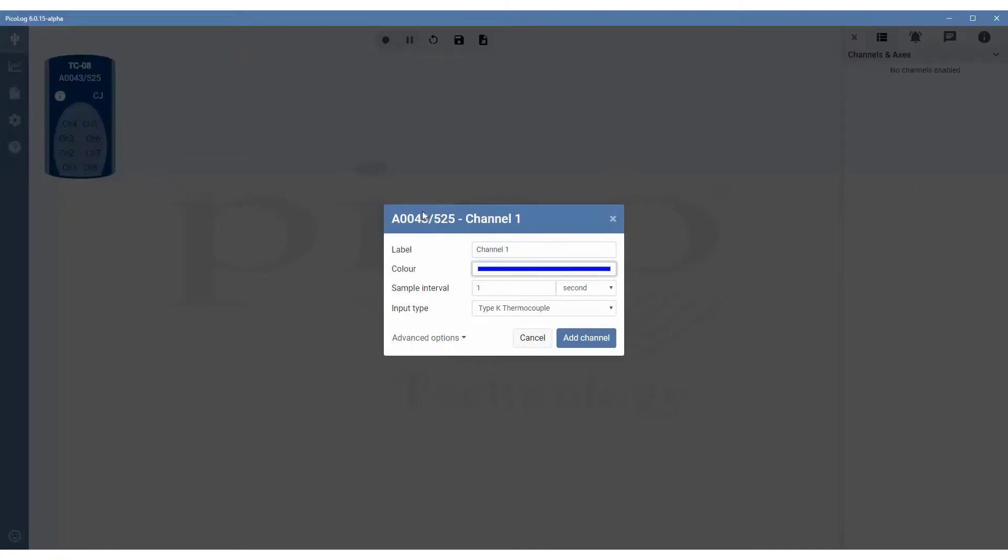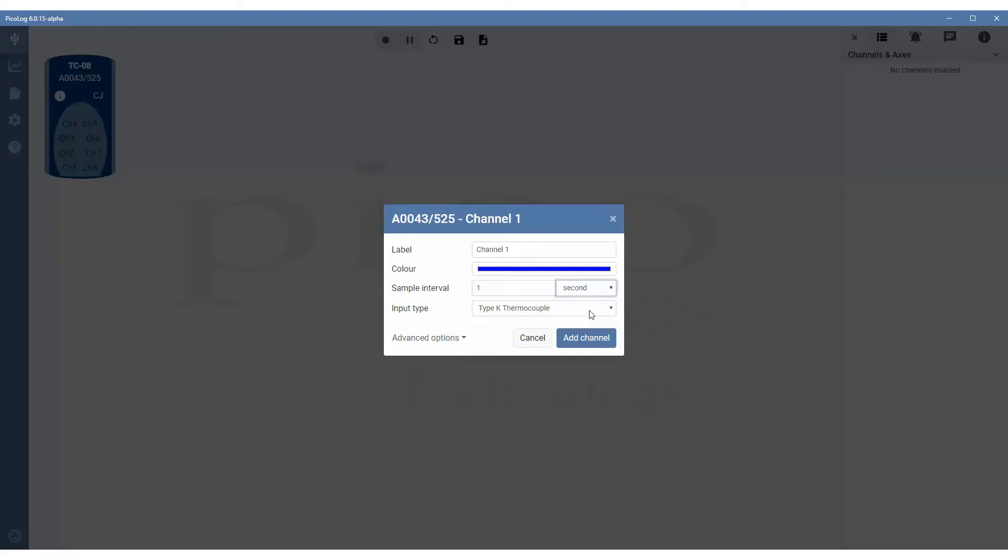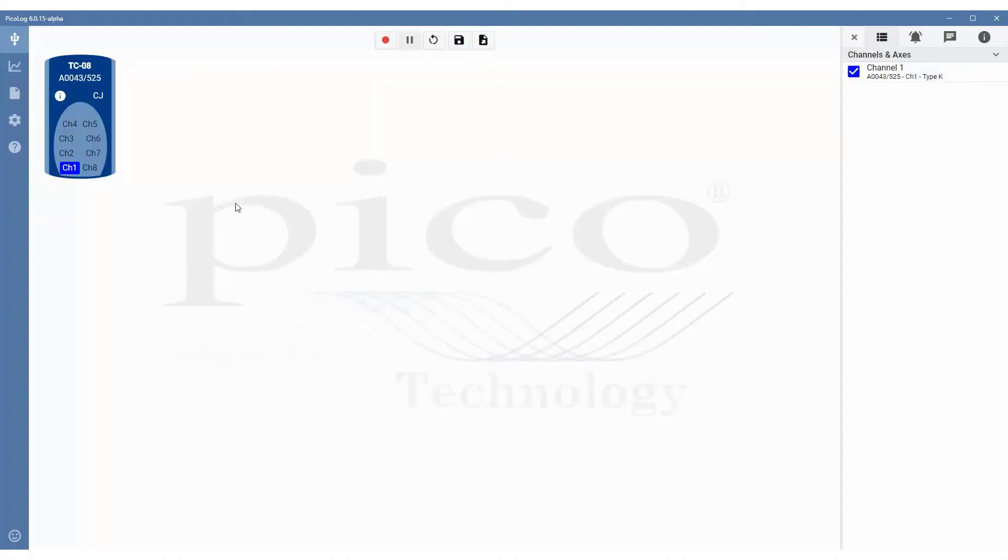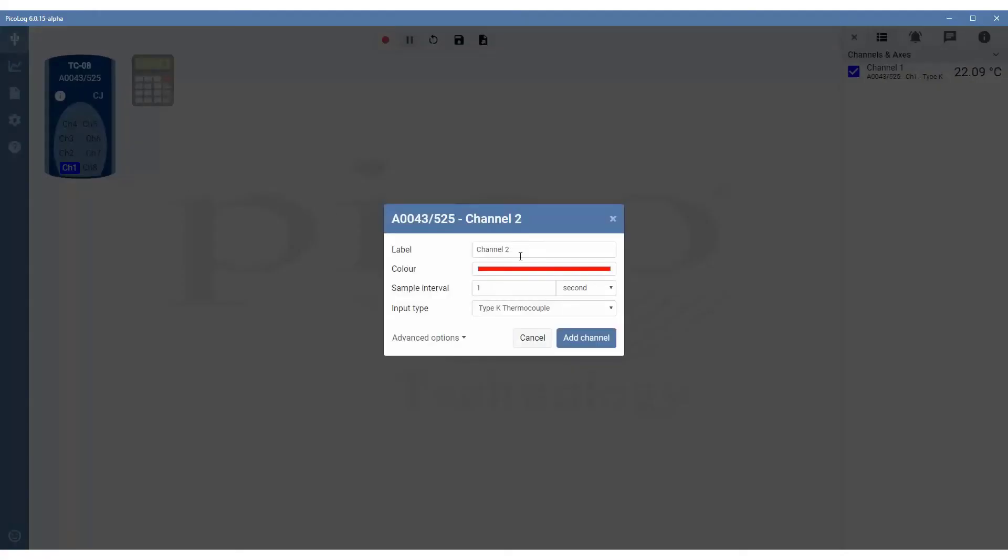We can also change the sampling interval. This can be milliseconds, seconds, or minutes. And you can also choose your thermocouple type. In this case, we're using a K-type thermocouple. Then you simply click on add channel. We'll do the same for channel 2. Leave everything else as default and then click on add channel.